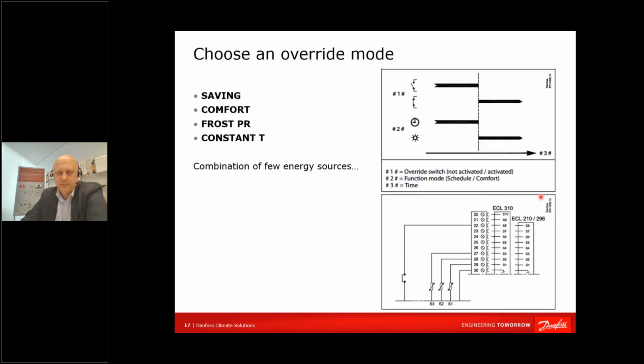Of course, the ECL should contain a key inside, otherwise it will lock itself and you will be unable to change anything. What else was convenient in ECL? You can have an external override switch by which you can turn ECL to saving, comfort, frost protection, or constant temperature mode. That is useful when you are combining a heat pump or something else, and you would like to place the ECL in a temporary mode where it is not heating the building and your heat pump is running. And when your heat pump is not capable of delivering more energy, then something might tell the ECL to come to business.